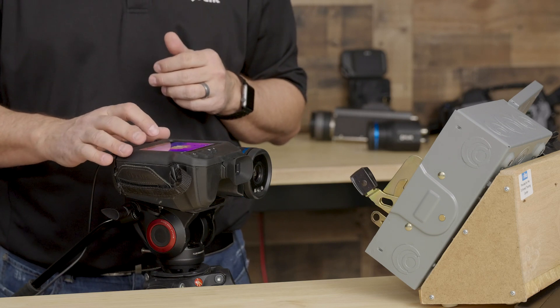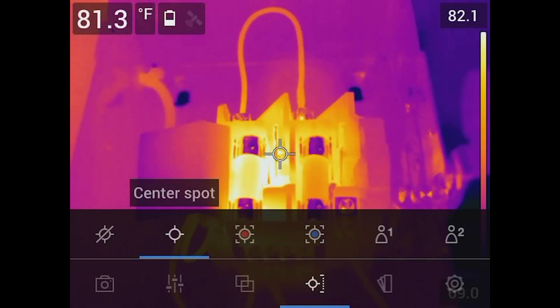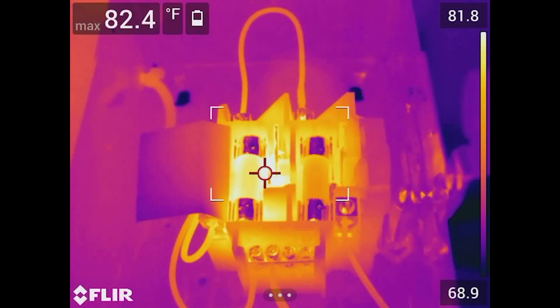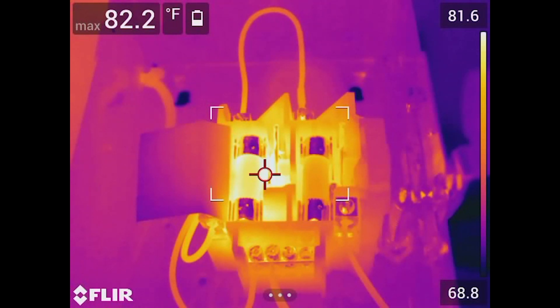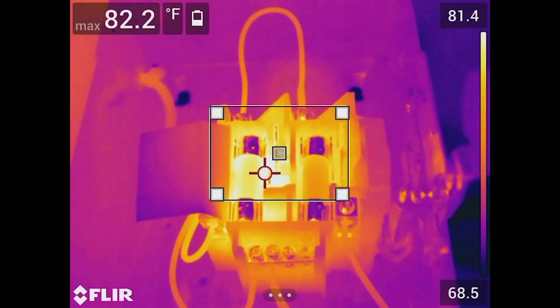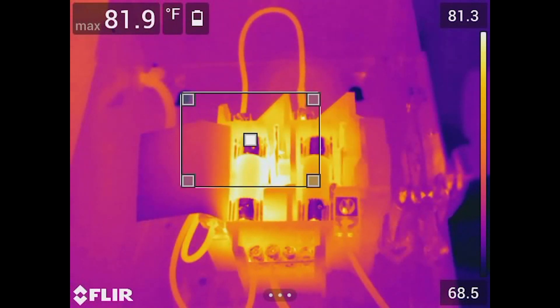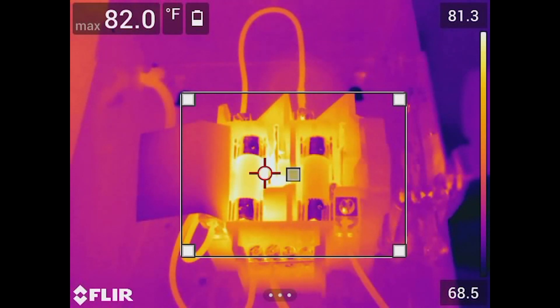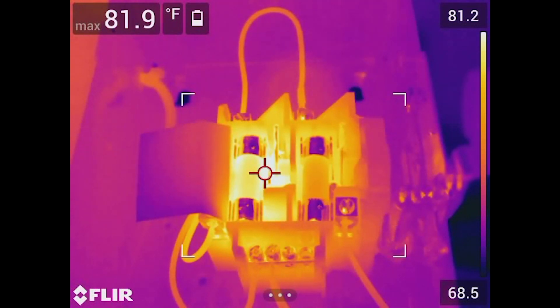As we move across our measurement functions, we have a couple of different options — one is red, one is blue. The red option gives us an area or region of interest. You can see there are four right angles on the screen with a red center spot moving around. The measurement feature is doing all the work for you — rather than guessing where the hotspot is, the camera finds it for you. We can move the box by touching it, or grab a corner to resize it to encompass a larger area, and it will find the hottest pixel.